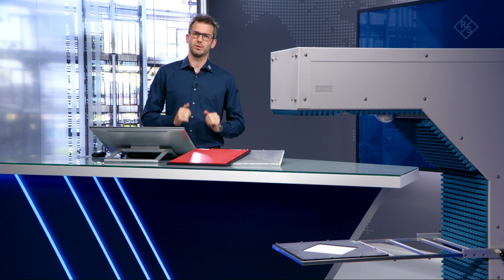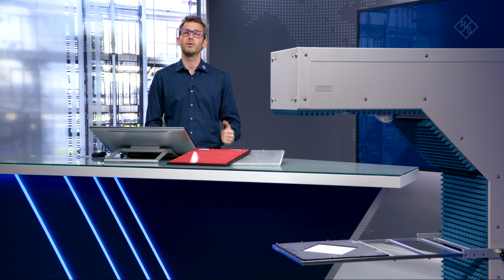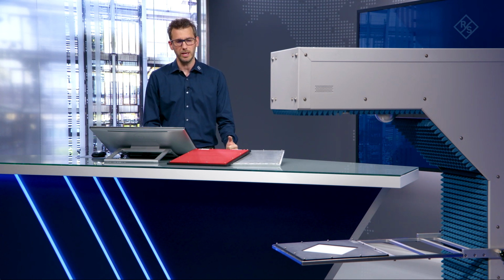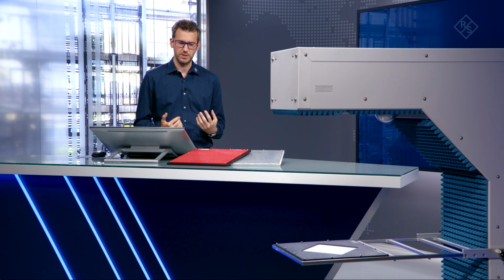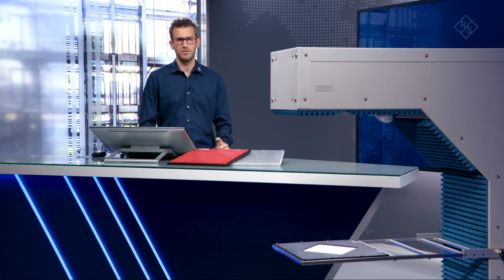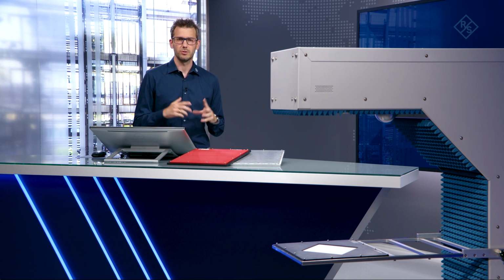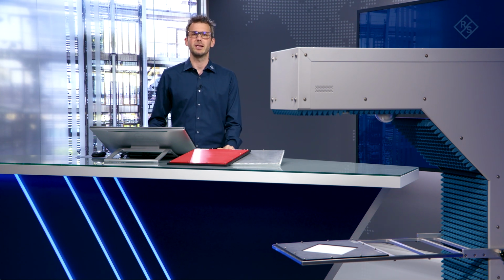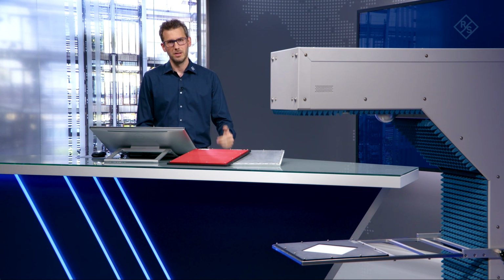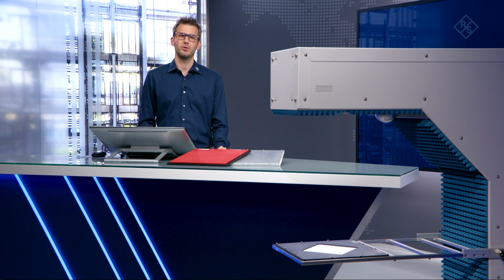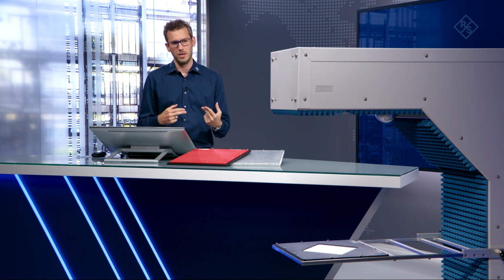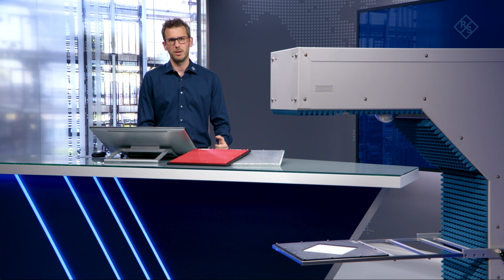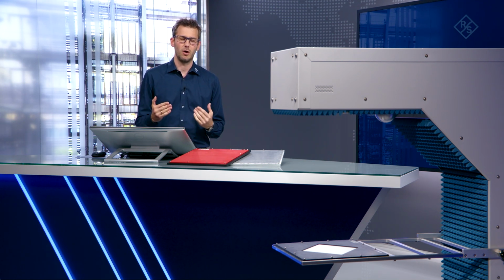So the values that are printed on the plates, they come from our experts in Memmingen and in Munich, and they are accredited. So that means the verification that you can perform with the QAR50 is accredited and traceable. So the results have absolute precision, which is an outstanding performance of the instrument. Therefore, there's also a respective video on the verification and on the accuracy and the traceability of the plates and how we are performing the accredited calibration in our plant in Memmingen.